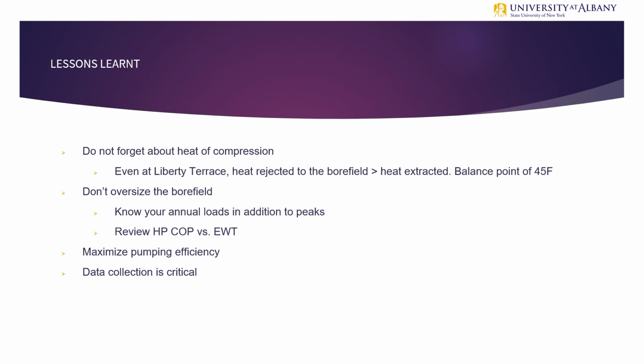And now this summer, we're actually taking out the gas-fired domestic hot water heater in that building and putting it on the geothermal bore field so we can extract more heat. So do not forget that. Do not oversize your bore field. Understand your load conditions. Unlike traditional systems where you're looking at just your peak load and designing your system for that peak load, that's not how you design a geothermal system. You have to look at your annual loads and the balance between the loads to figure out how much storage do I need? What is this bore field providing for me in this system, and design it for that. Because the problem that we have is when we oversize, it becomes super expensive, and then people are like, oh, it's not going to work for us. No, it is going to work if you design it properly.